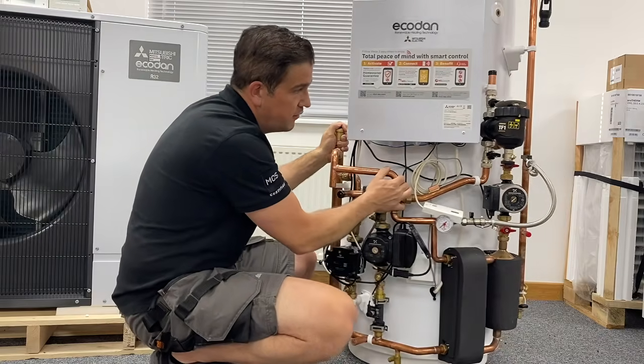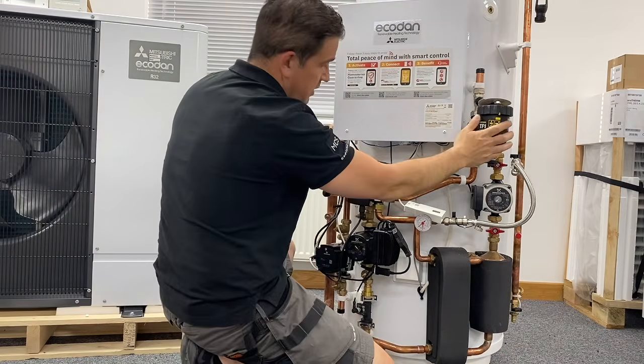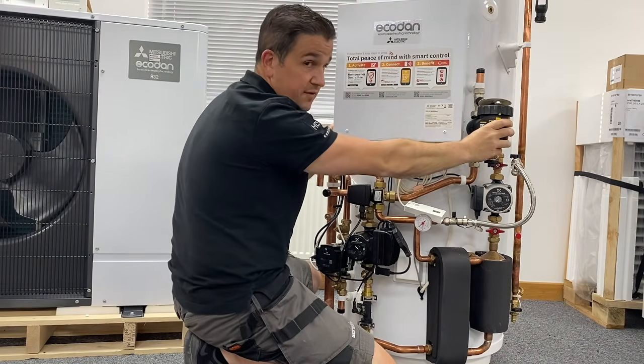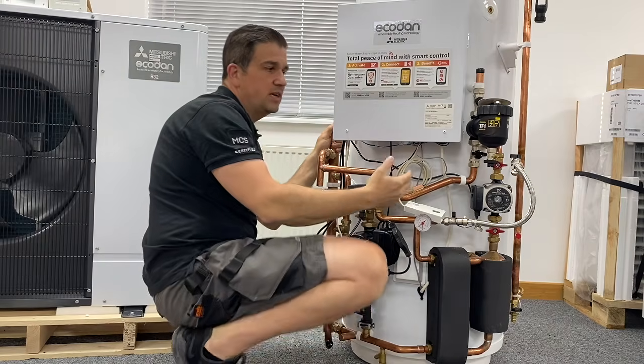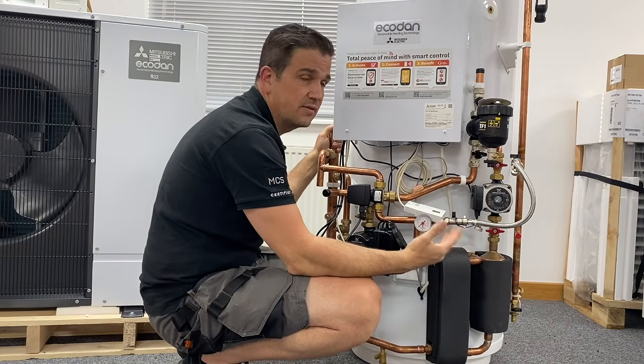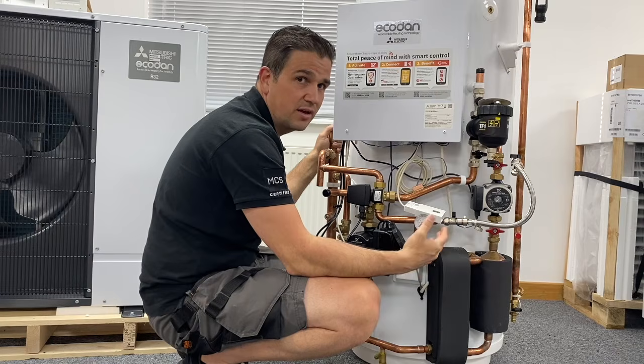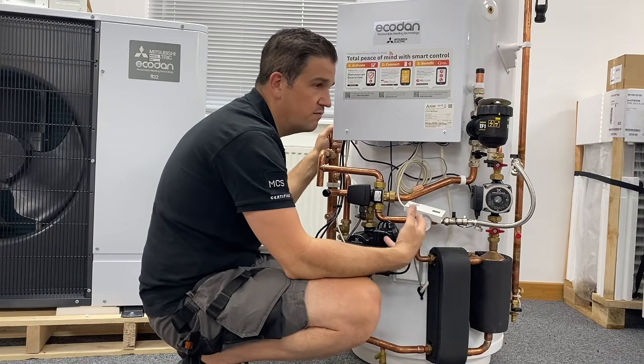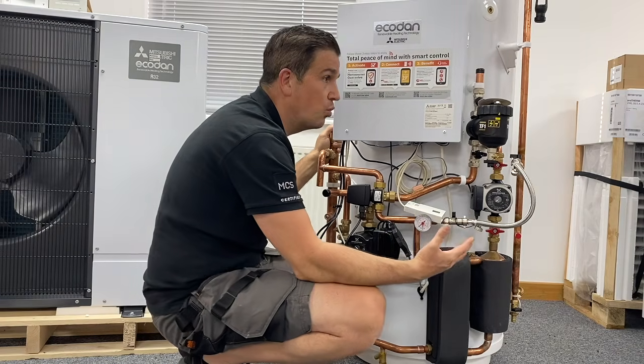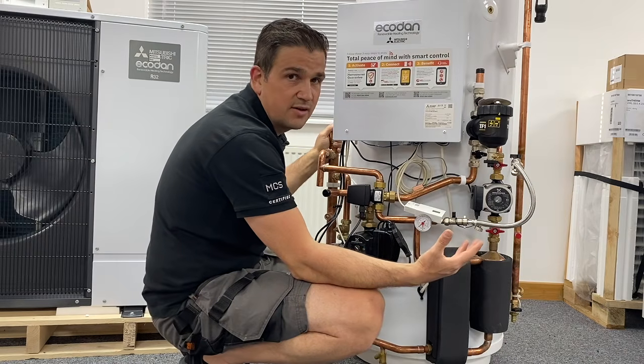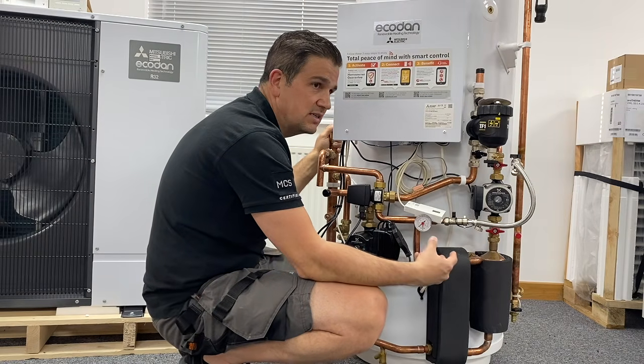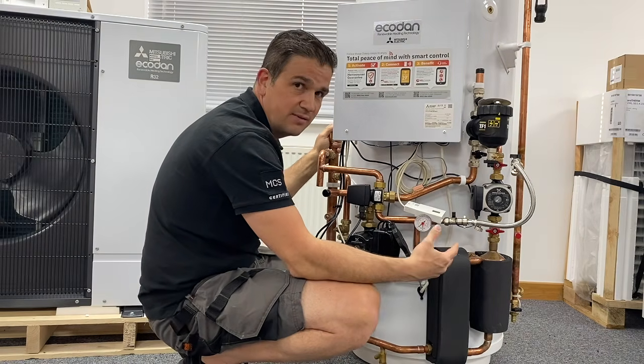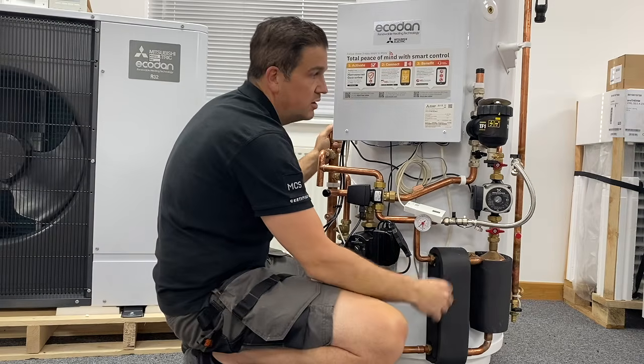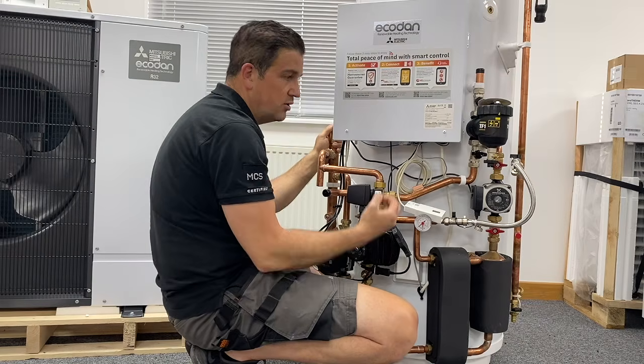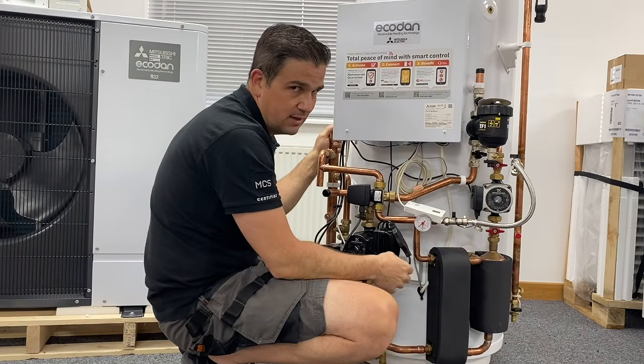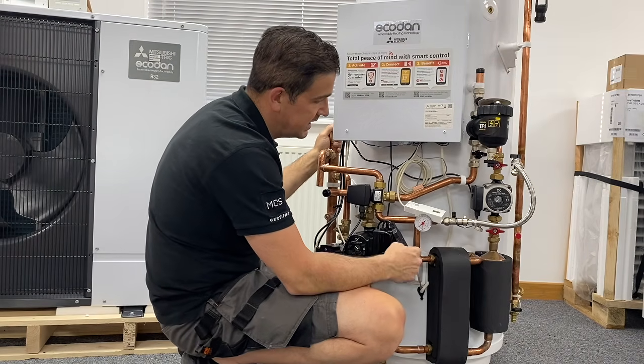Then on the front here, we've got a magnetic filter. This enables us to keep the system efficient and clean from any debris, particularly from radiators, you know, magnetite and stuff like that. But if everything's inhibited or protected properly, you shouldn't really have too much of an issue. This will just pick up any small debris or any shards from inside the radiators or whatever. That helps protect it.